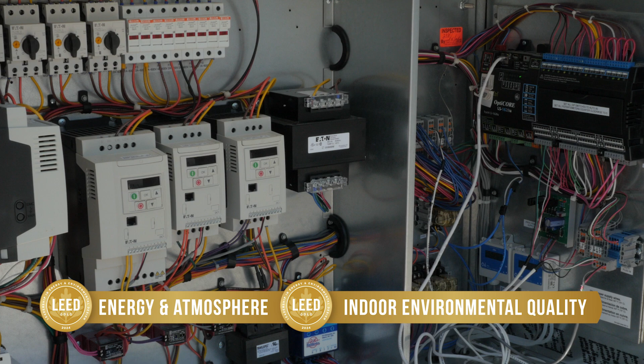A feature special to VRF units is their ability to transfer heating and cooling within the building. The VRF system can extract heat from one room and move that heat to another room where it's needed. This allows for significant energy savings over conventional heat pumps.